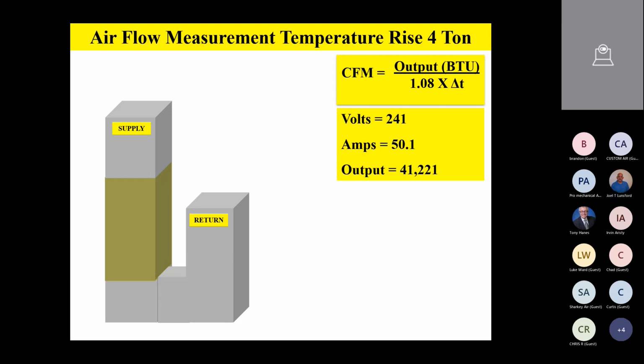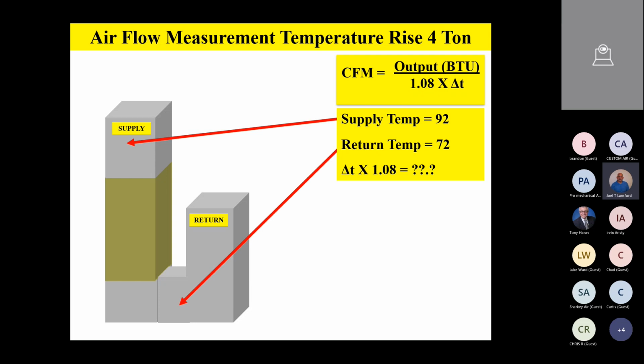41,221 is the number I've got, so you should be real close to that. Next step, we're going to measure our supply and return air temperature. In our example here, we've got 92-degree supply air temp, 72-degree return air temp, and we find the difference. That's the delta T portion of the formula. The difference between 92 and 72 is 20.